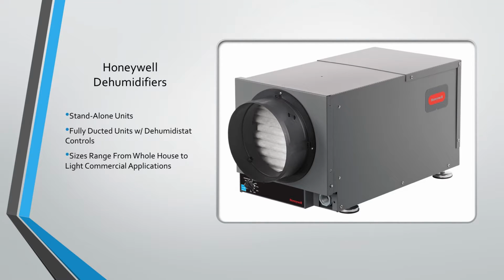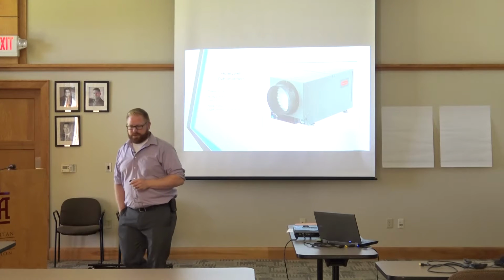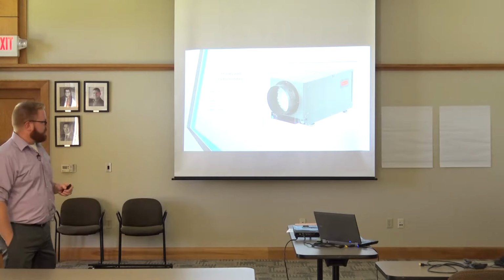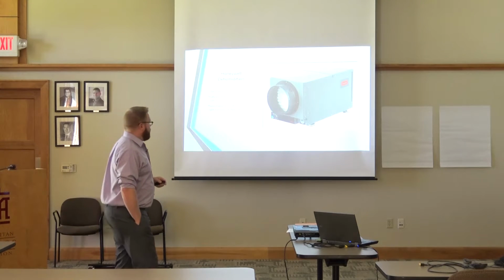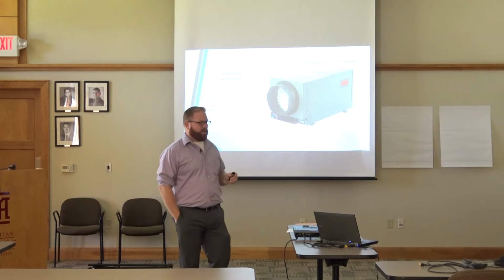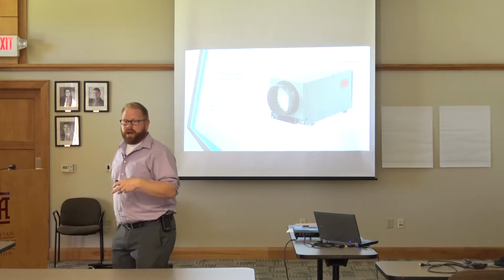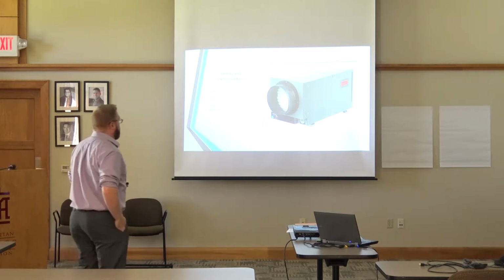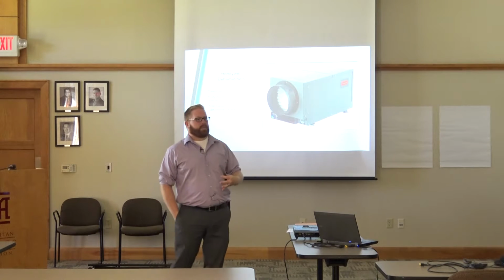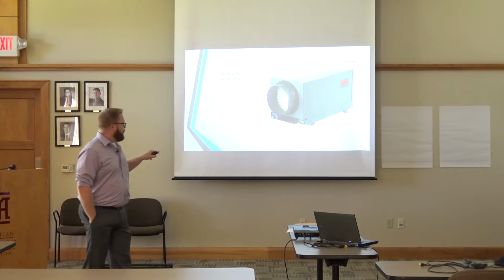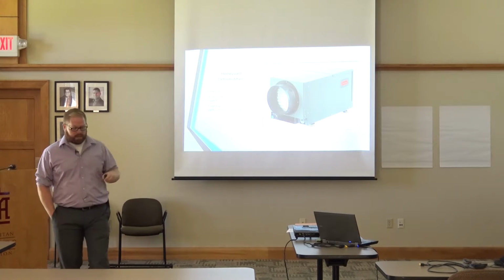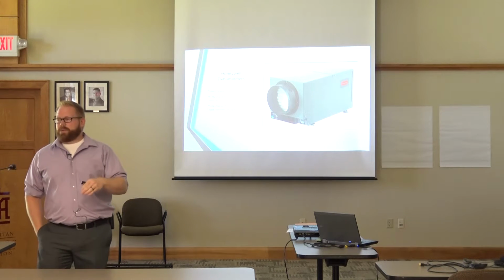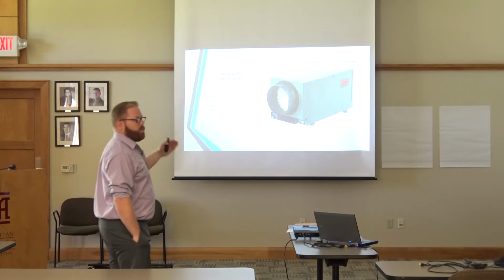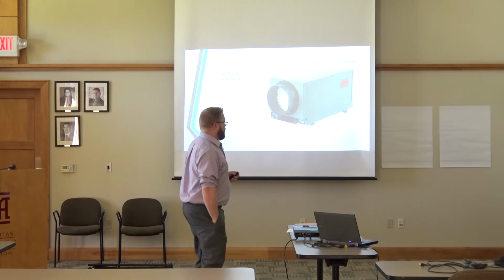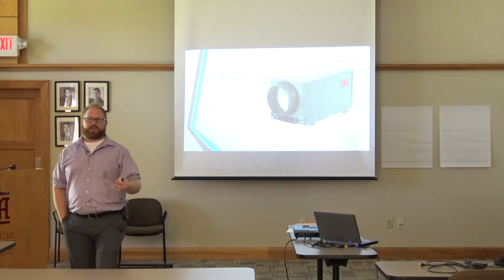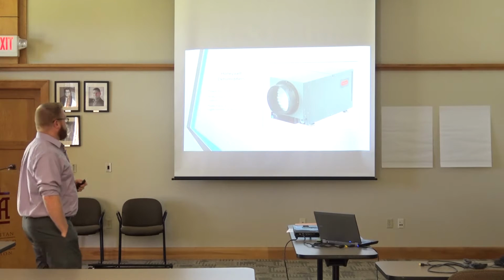Dehumidifiers are also becoming more popular to tie into duct systems and HVAC systems, to get a whole house dehumidifier. These can be used as a standalone model or ducted directly into your return and supply to help pull the moisture and humidity out of the air, which helps reduce air conditioning run times. We've also found that installing whole house dehumidifiers in line with the systems actually reduces our cooling load in the home because we're removing that much more humidity. So when we do our manual J calculations on those houses, we're actually seeing we can reduce the overall tonnage of the air conditioning systems.